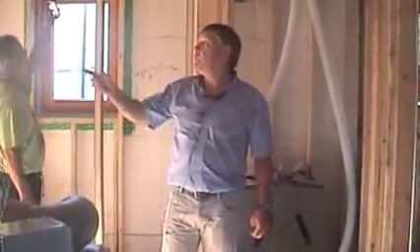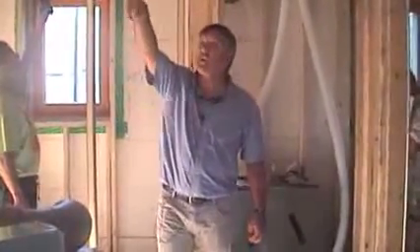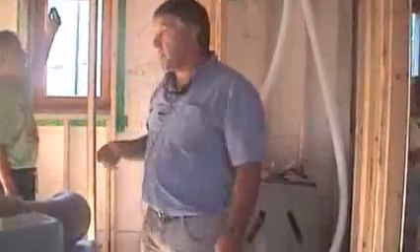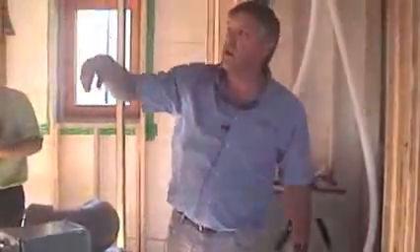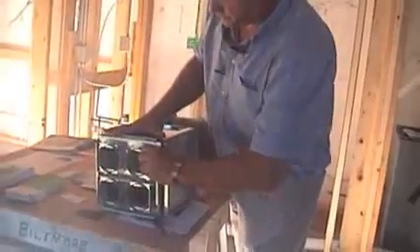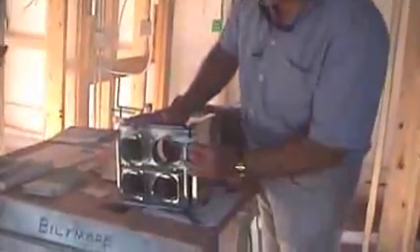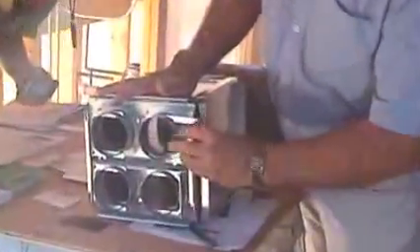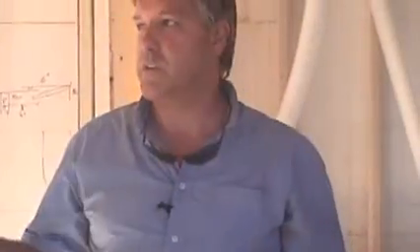Okay. So they've put all the diffusers in. Now they're just starting to run the ducting. And this ducting, you can see some of it's hanging over there. There's an O-ring that is mounted right around the last ring on it. And that O-ring system is a clip. It slides right in there with an O-ring seal, and you just clip it into the next ring on the tube, and that's how it is put together. Leakage is 0, and it just goes right together.